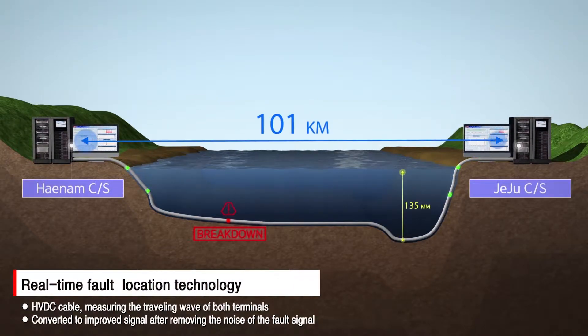First, real-time fault location technology is an innovative detection technology using wavelet transform. Surge traveling waves occurred in HVDC cable are measured at both terminals respectively, and the measured complicated fault signal is converted to simple signal without noise through self-developed algorithm process. The fault location is finally calculated with improved accuracy.